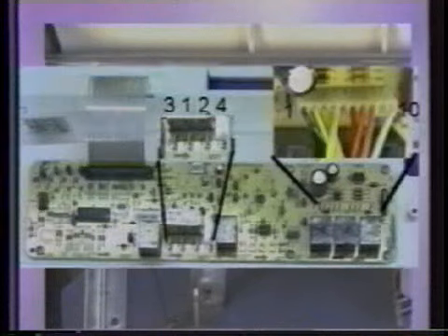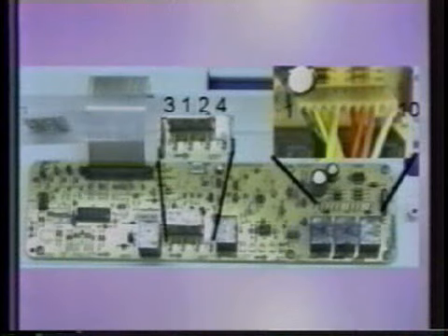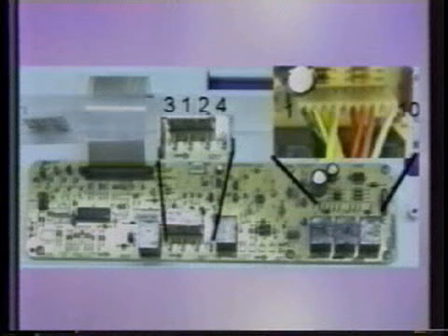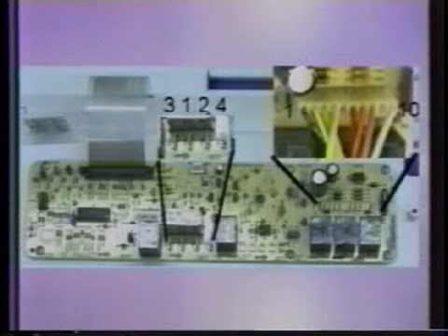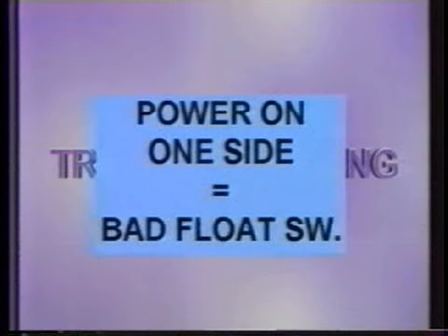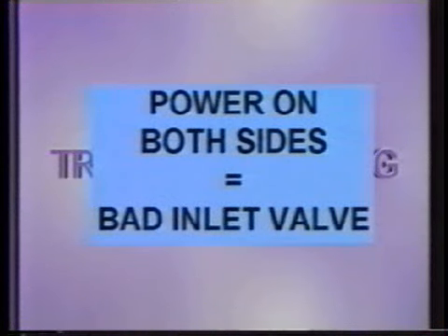If I do not have any voltage, I would go back to my board and measure power out of pin 8 of the 10-pin plug. Here, if I do not have any voltage, I got a defective board. If I do have voltage at this point, I've got a broken wire going down to the float switch. If I have power on one side of the float switch but not on the other, I have a defective float switch. If I have power on both sides of the float switch, I then know that I have a problem with the water inlet valve.